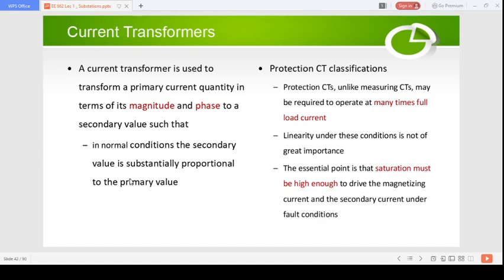Let's take a look at the current transformer. The current transformer is used to transform a primary current quantity, in terms of magnitude as well as phase, to a secondary value, such that in the nominal condition the secondary value is substantially proportional to the primary value. So you have a primary current, which is basically the current flowing in the bus bars in the substation and the lines, and then you convert these currents into more readable currents in order to do the measurements as well as to activate the protection and the control.